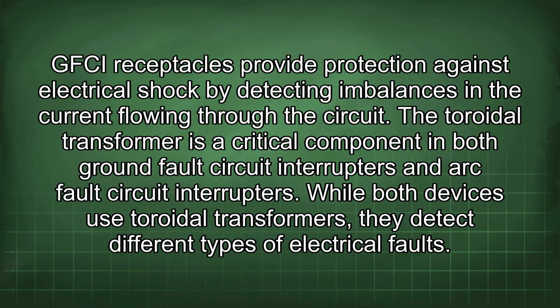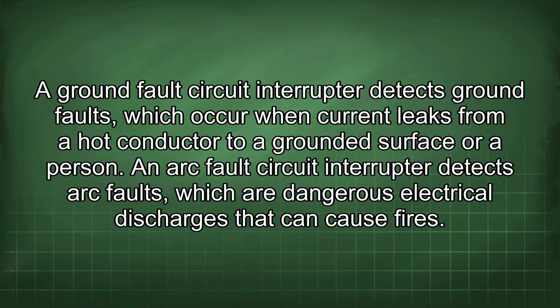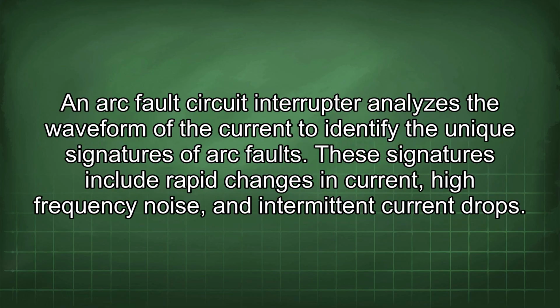The toroidal transformer is a critical component in both ground fault circuit interrupters and arc fault circuit interrupters. While both devices use toroidal transformers, they detect different types of electrical faults. A ground fault circuit interrupter detects ground faults, which occur when current leaks from a hot conductor to a grounded surface or a person. An arc fault circuit interrupter detects arc faults, which are dangerous electrical discharges that can cause fires. An arc fault circuit interrupter analyzes the waveform of the current to identify the unique signatures of arc faults. These signatures include rapid changes in current, high-frequency noise, and intermittent current drops.